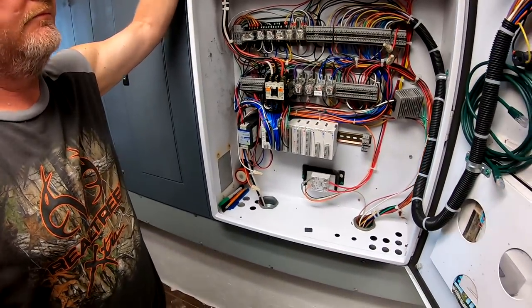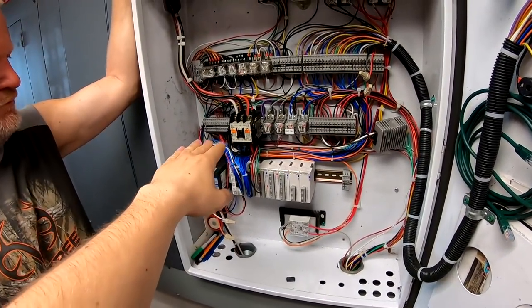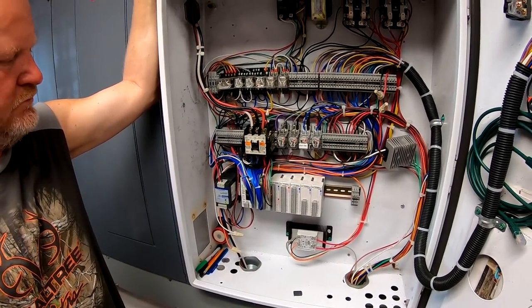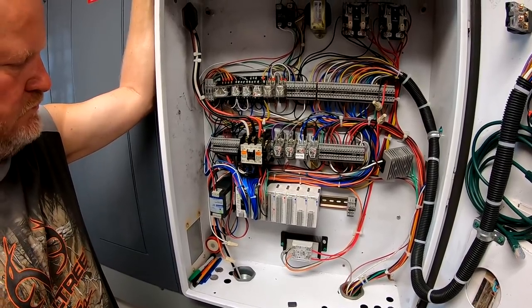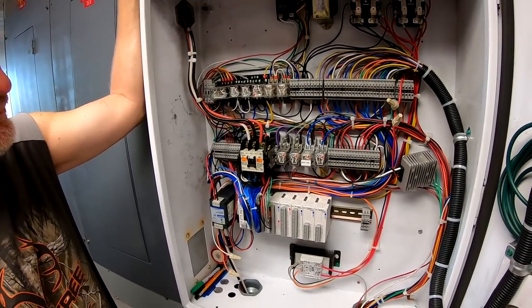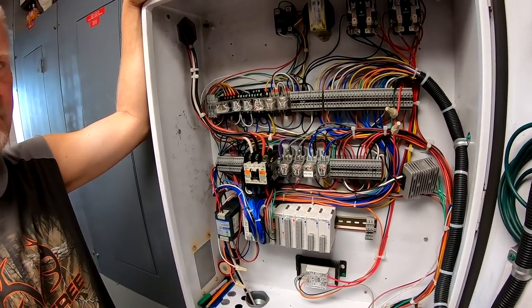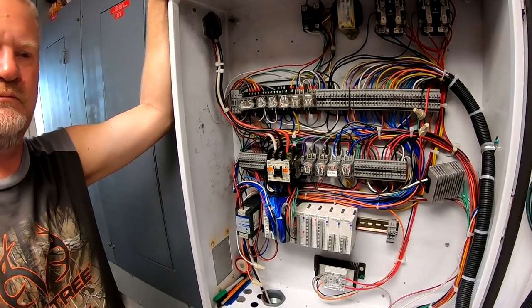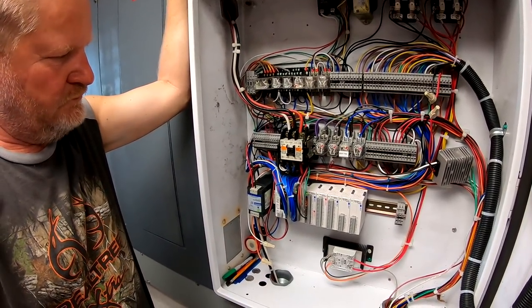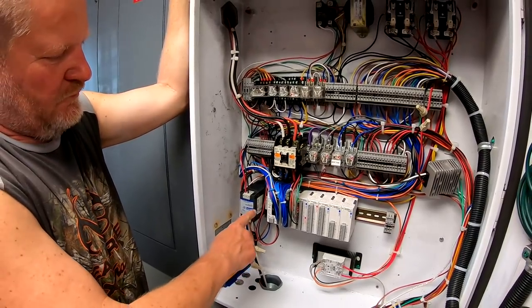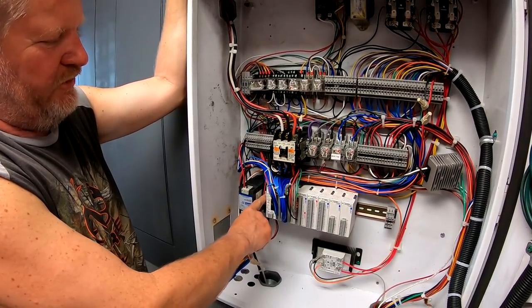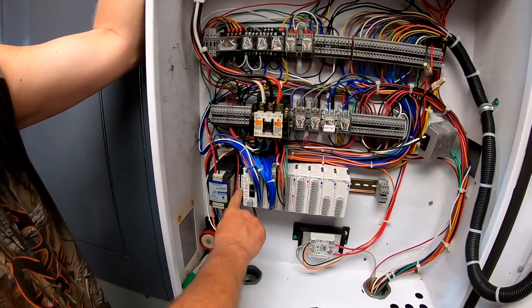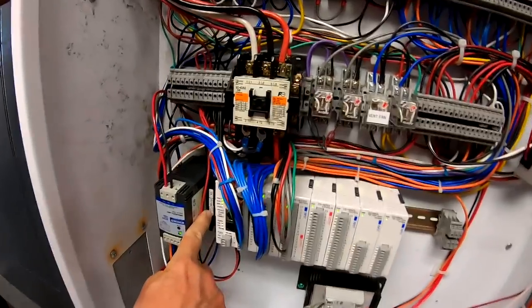But I actually found the other day online that we can get this relay in 24 volts DC and eliminate this one and just control it right off the PLC. And then if this is DC, because right now this is powered off 24 volts AC which comes from this transformer up here. Well what happens is if the power goes out, we no longer have enough voltage or anything to control that contactor.